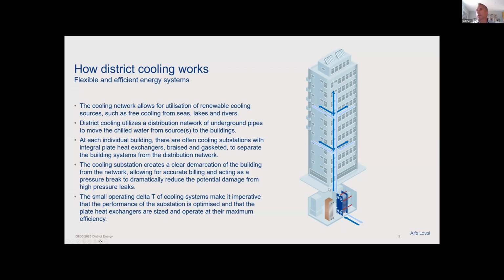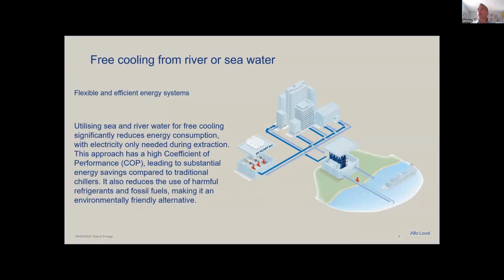And we can see here, this would be a typical substation application in the base of the building. And as we move through the different options, this is one which I'm going to show a little case study on at the end, but this is free cooling. You have some plate heat exchangers here to the district cooling plant and then distributed out. That's exactly what's been done in Toronto from Lake Ontario, which we'll look at a little bit later. And that gives you major benefits in terms of the COP of the overall system itself.